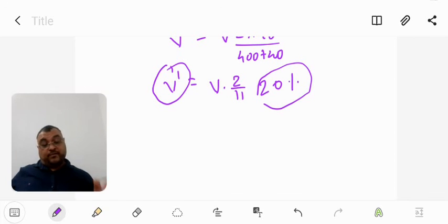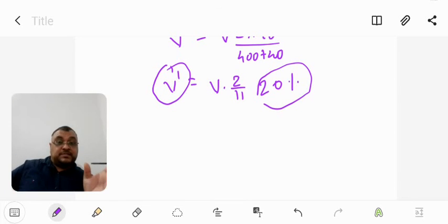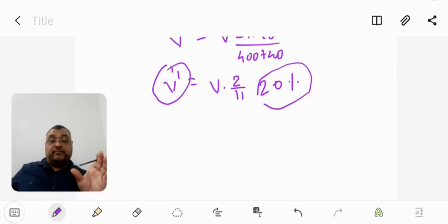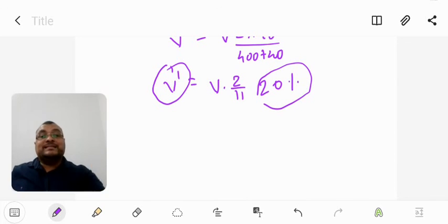This small amount of voltage passes only because of this cable connection. If you don't connect this cable, the entire wave is reflected to the equipment, which may damage it. So, as we know, at each and every substation, the transmission line ending is terminated with a cable due to this advantage.